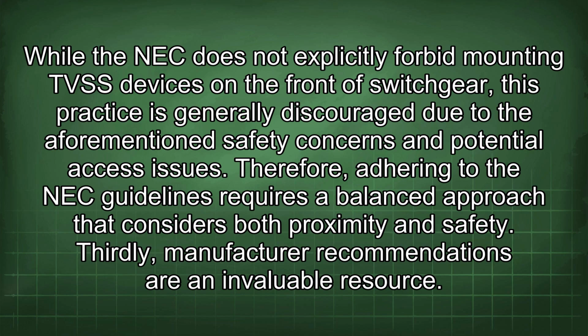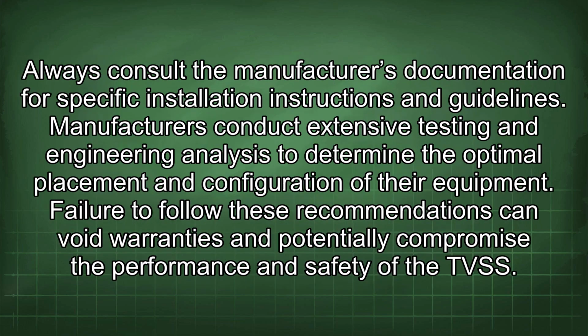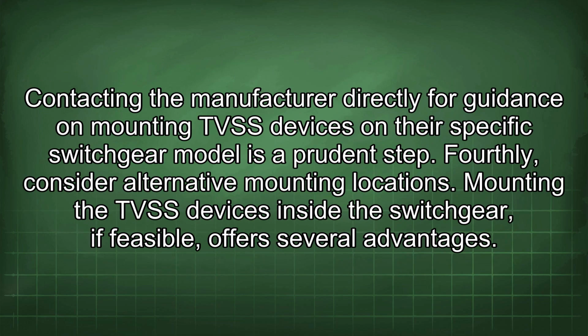Thirdly, manufacturer recommendations are an invaluable resource. Always consult the manufacturer's documentation for specific installation instructions and guidelines. Manufacturers conduct extensive testing and engineering analysis to determine the optimal placement and configuration of their equipment. Failure to follow these recommendations can void warranties and potentially compromise the performance and safety of the TVSS. Contacting the manufacturer directly for guidance on mounting TVSS devices on their specific switchgear model is a prudent step.